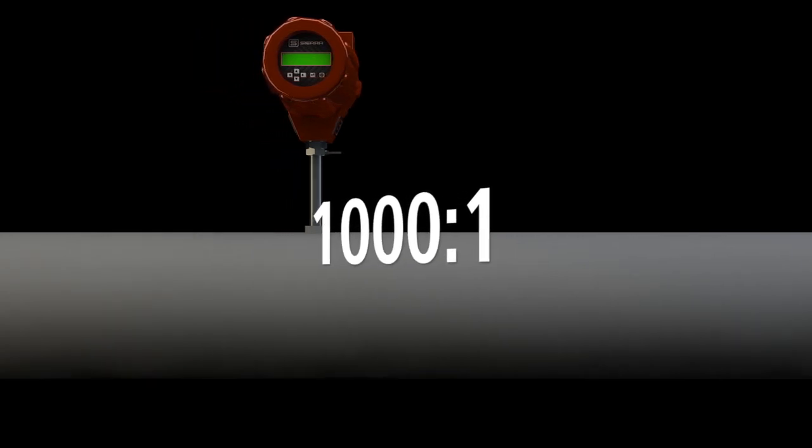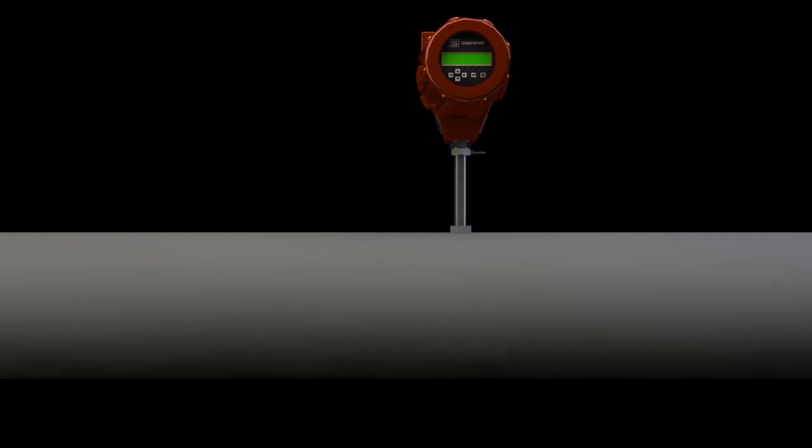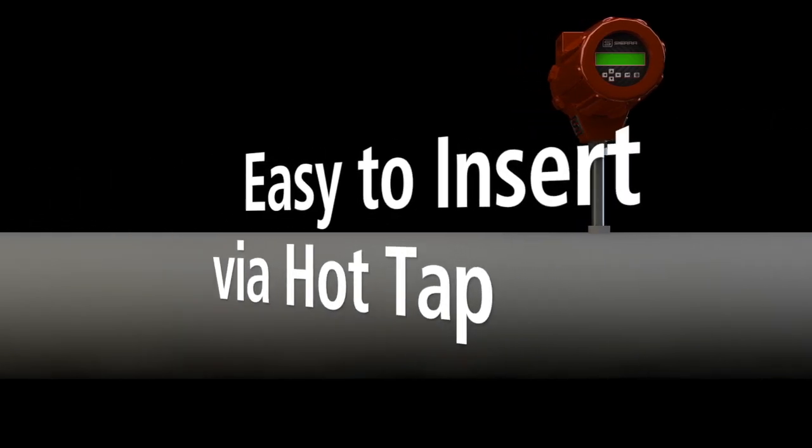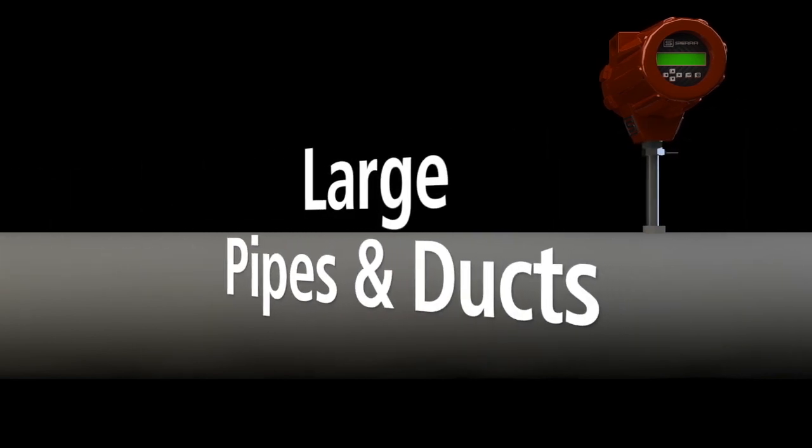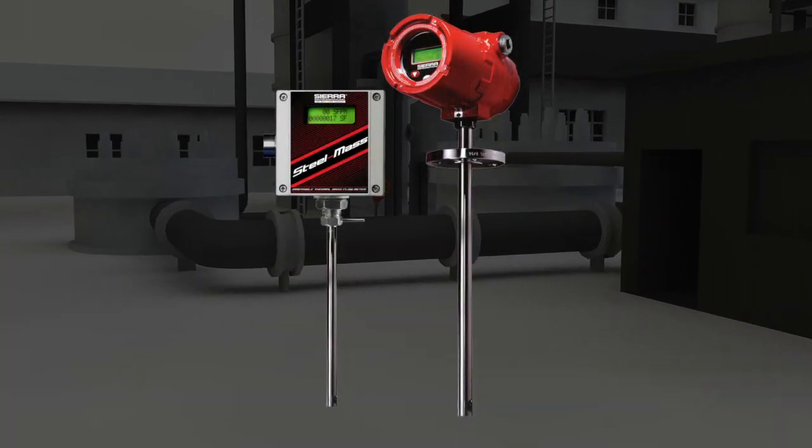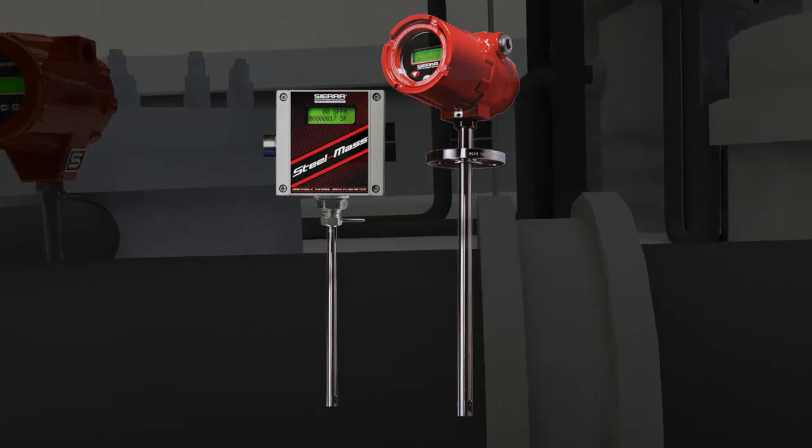In addition to accuracy, thermal flow meters have become extremely popular due to high turndown, up to 1,000 to 1, giving the ability to measure very low flows up to very high flows with the same instrument. Since they are rugged and reliable, have no moving parts, are easy to insert via hot tap, have negligible pressure drop, and offer an economical solution to large diameter pipes and ducts, thermal technology has been rapidly adopted over the last decade.